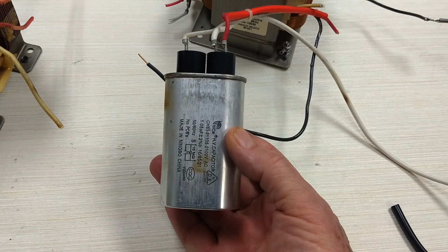Oh, I just remembered another potential hazard from the capacitor. This type of capacitor is filled with oil, as are capacitors and transformers that you see hanging on utility poles. This oil can be a very nasty type; they used to use oil that was carcinogenic. You can see this little dot of solder here, that's plugging the hole where the oil was injected into the capacitor. So never, ever open one of these up. Just think there's deadly stuff inside, and you don't want to mess with it.